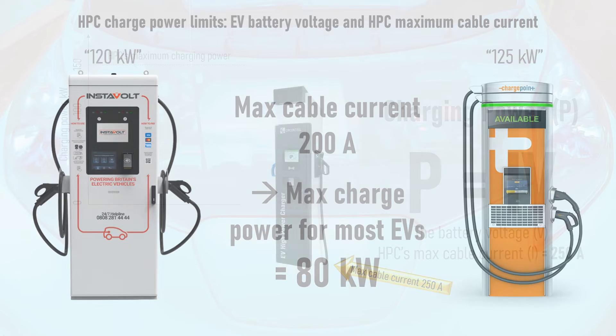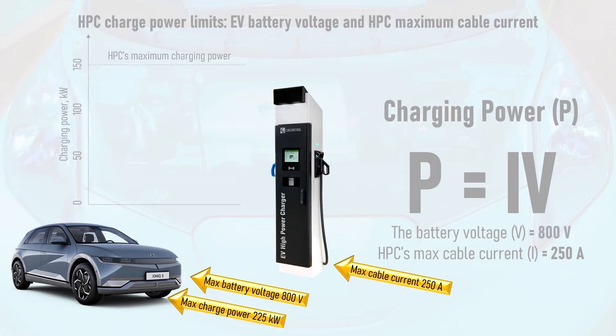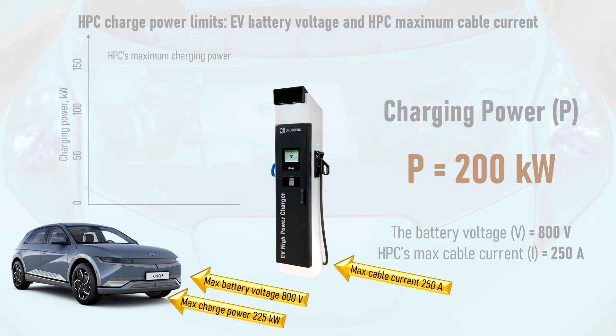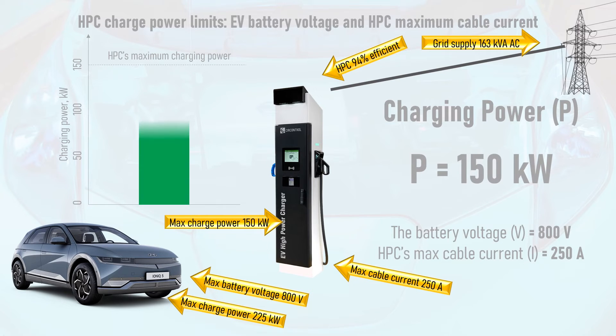Speaking of the IONIQ 5, which has an 800V battery pack and a maximum charge power of around 225kW, if one were to plug into a Alpitronic Raption 150, the maximum achievable charging power in theory would be 250 amps multiplied by 800V, which is 200kW. But this exceeds the grid supply to the HPC, which is designed to be installed with a 163kVA AC grid connection. Since the charger itself is 94% efficient, this translates to its headline maximum charge power of 150kW, which the IONIQ 5 will draw in full.